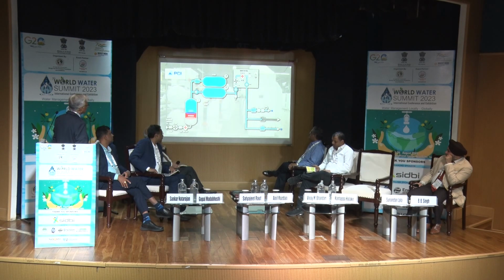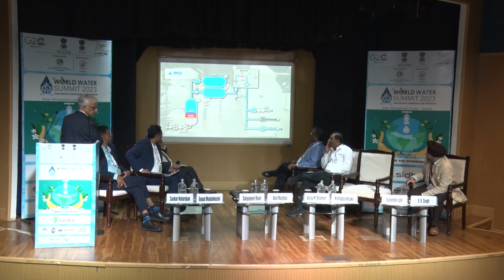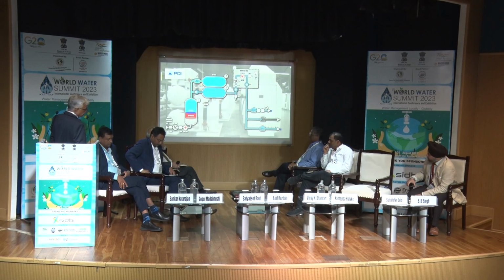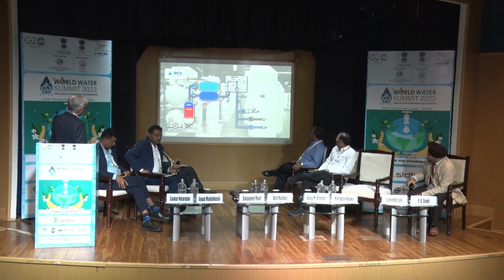This is that particular VSA technology, my last slide. On the left-hand side, you will see a chamber, and there is a blower. Instead of a compressor, we have just a blower. It withdraws the air from the atmosphere through a heat exchanger. It goes to the chamber where you have molecular sieve, and oxygen is generated, and nitrogen is absorbed, and oxygen is driven up to the two tanks.